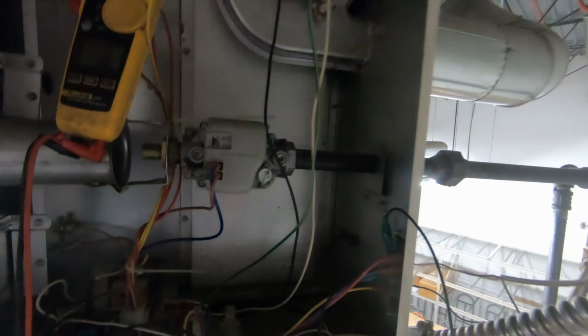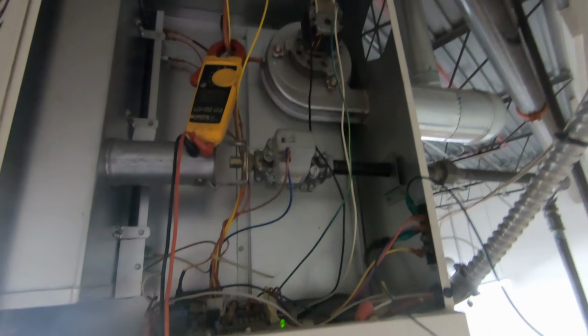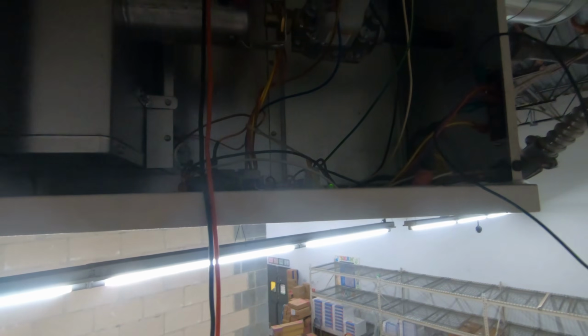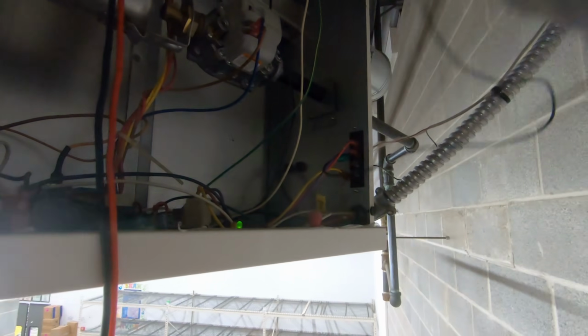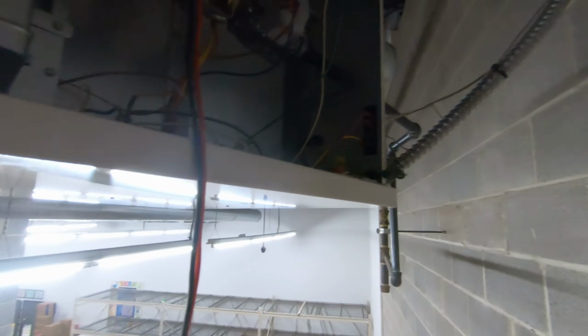All right guys, I had to disconnect the call for heat and jumped out G, and then it allowed the blower to run. So our blower runs, our board looks like it's in decent shape, combustion blower's shot, the rollout switch is closed. The only last thing to check really is to attempt to get along this side and get a look at this heat exchanger, but I don't know that I'm going to be able to do it safely.